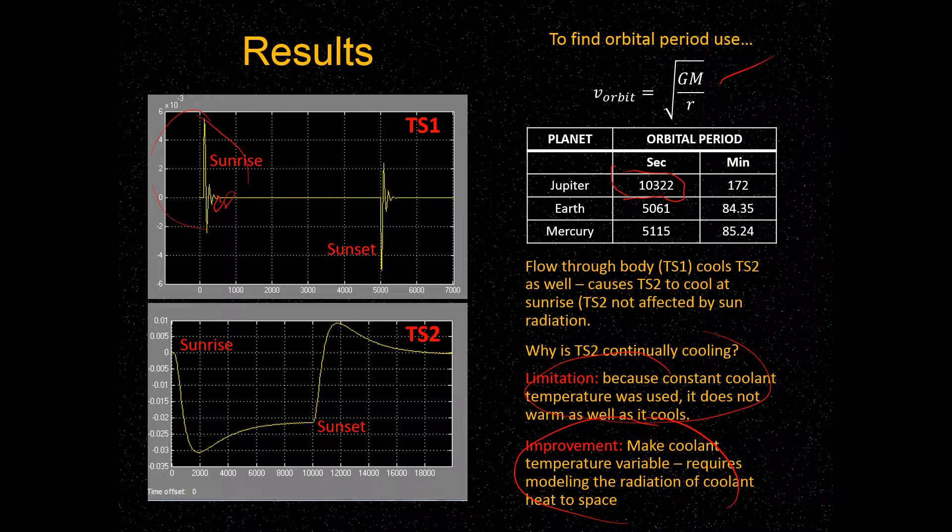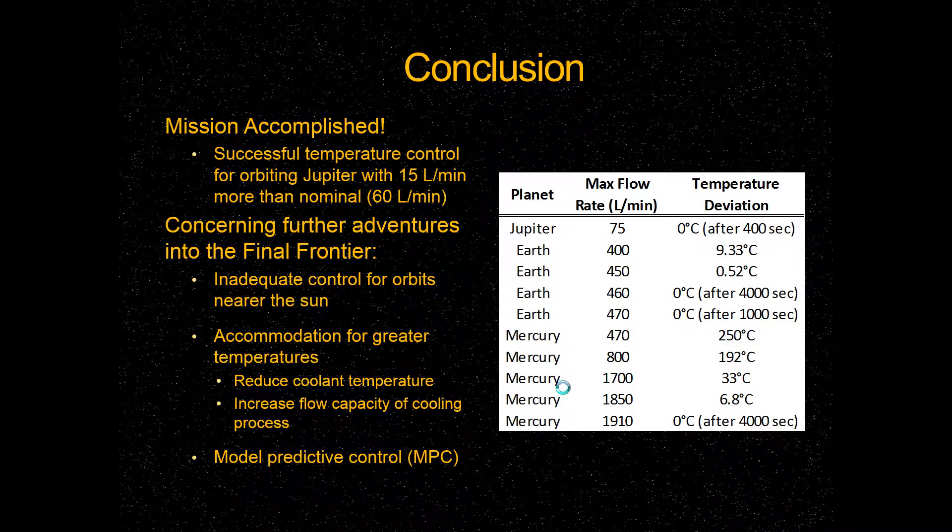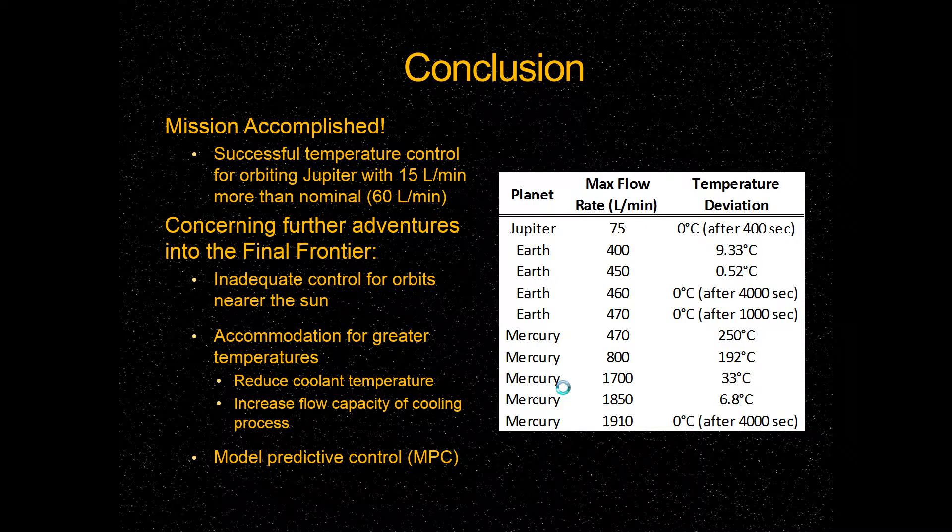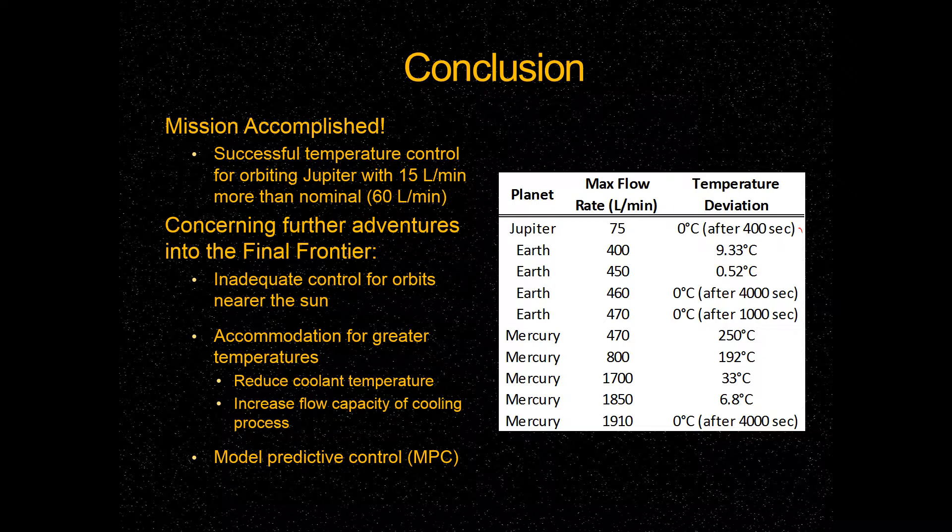As Ben said, we were able to accomplish our objective, and we were successful in controlling the temperature within a tenth of a degree. And you can see right here, that was within 400 seconds, after 400 seconds. And our nominal flow rate was 60 liters per minute, but to reach the results on the previous slide, we used 15 liters per minute more than the nominal flow rate. And it was very successful in controlling the temperature.